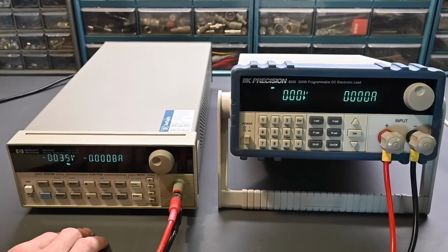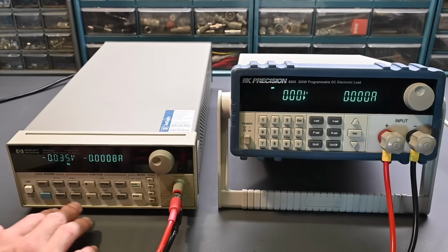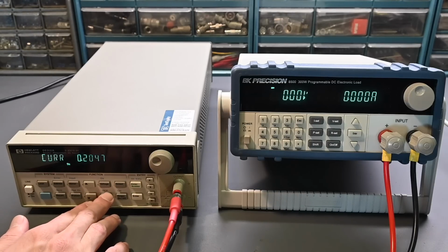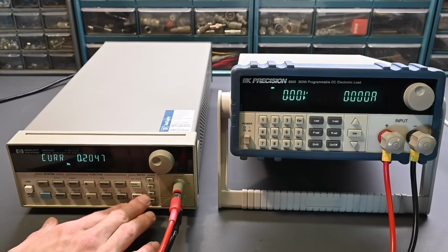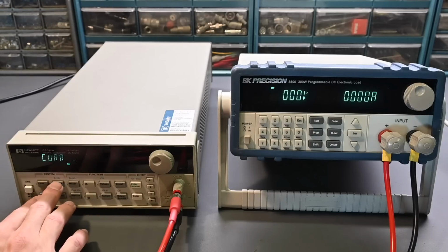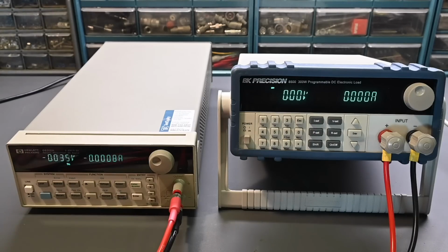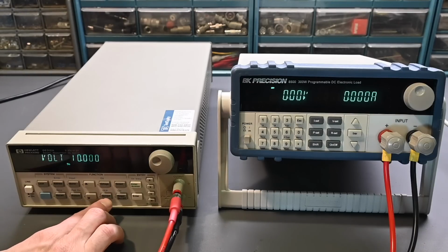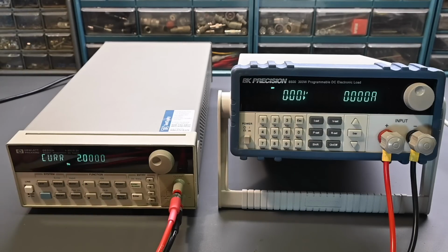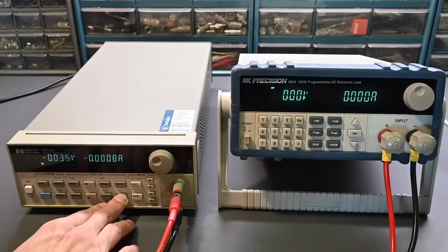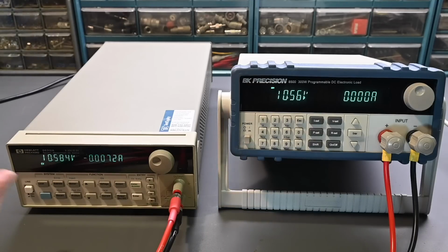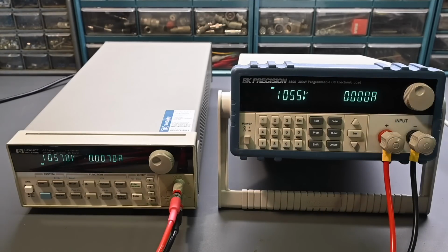And the current, let's put the current up to 2 amps. So we'll go here, it's the output current, and we will go number entry 2 and enter. So that should be perfectly fine. So you can always check those values. If you hit voltage, it's at 10. Current is at 2, so everything looks good there. So let's output on off. I don't know if you can hear the fan is running also in the power supply, but the microphone might be blocking out that noise. It has a noise canceling.